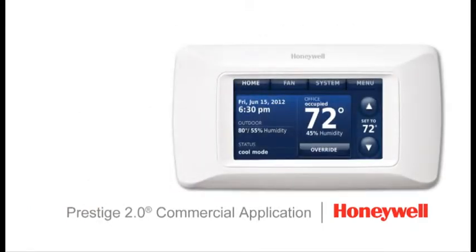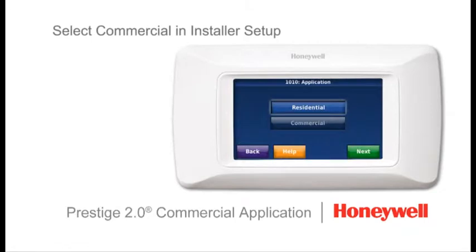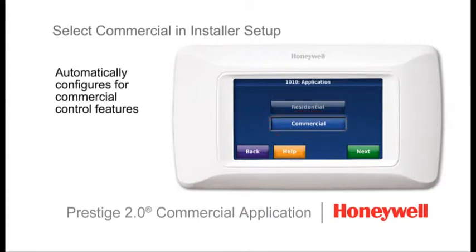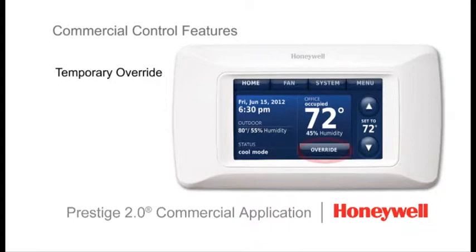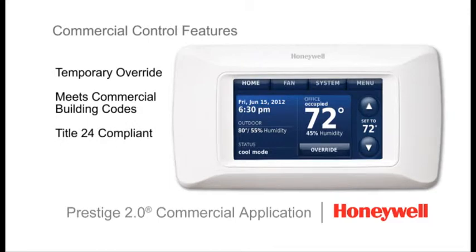Let's take a look at how Prestige 2.0 can be configured for commercial applications. First, let's get into the installer setup. By selecting the commercial option, Prestige 2.0 will automatically configure itself to enable commercial control features, such as eliminating permanent hold and replacing it with temporary override to meet commercial building codes and to be Title 24 compliant.